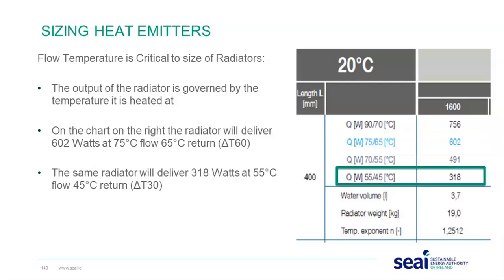Whereas, where we look at it with a flow temperature of 55 and a return temperature of 45, which is a delta T of 30 degrees, we can see it will only deliver 318 watts. So we can see the output is significantly lower when it's run at a lower temperature. So the principle of this is essential when we look at heat pumps.